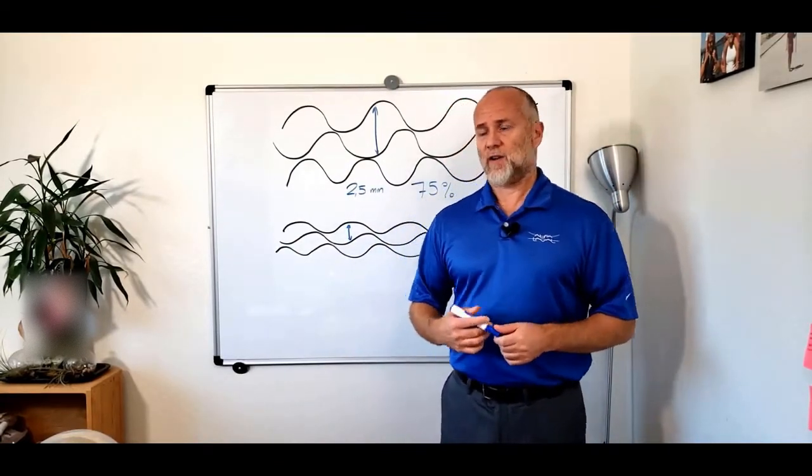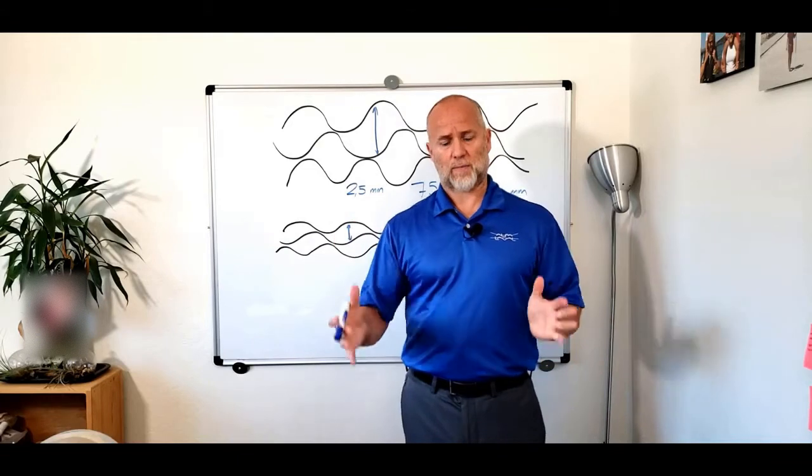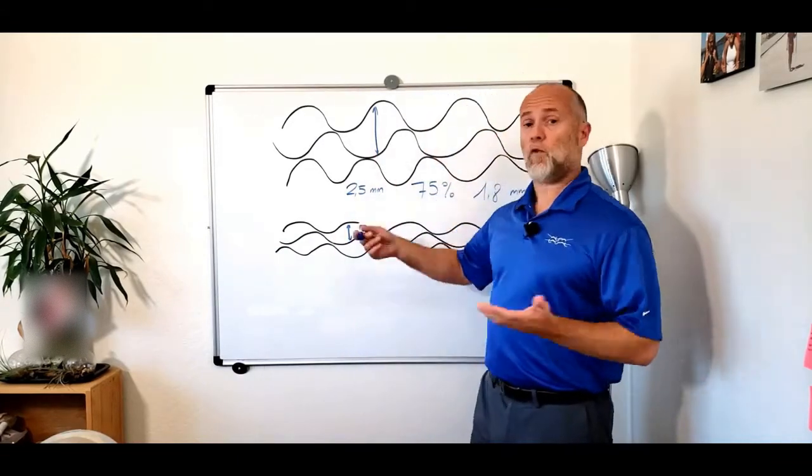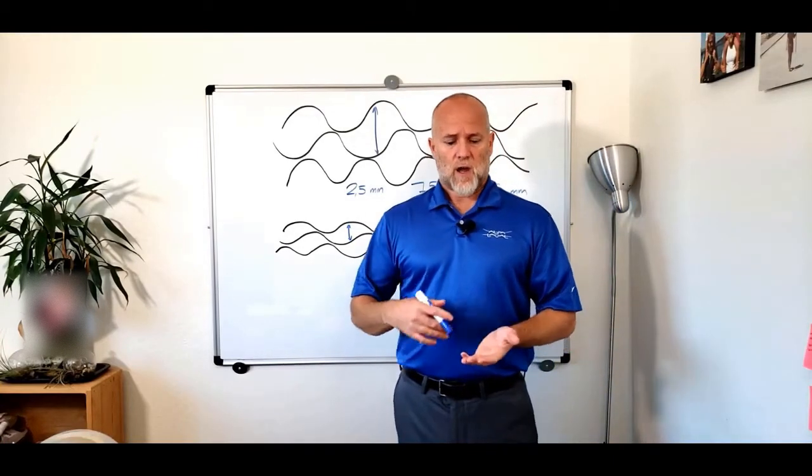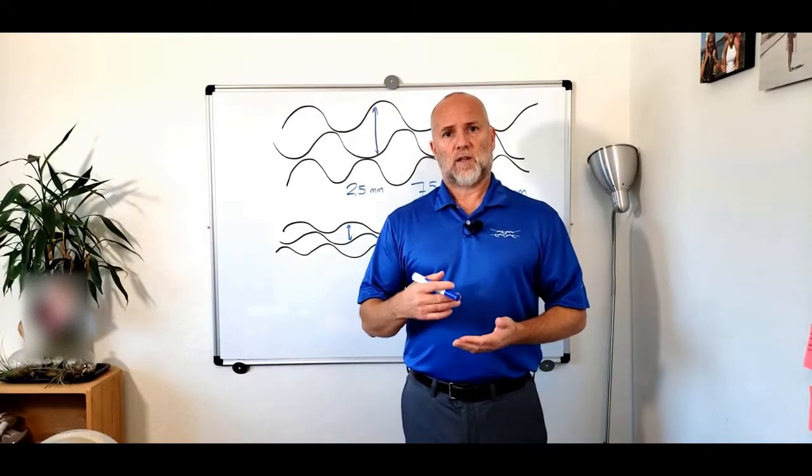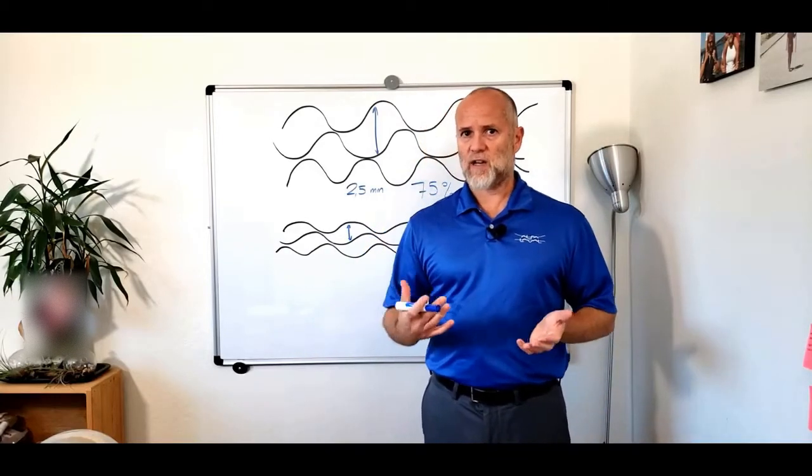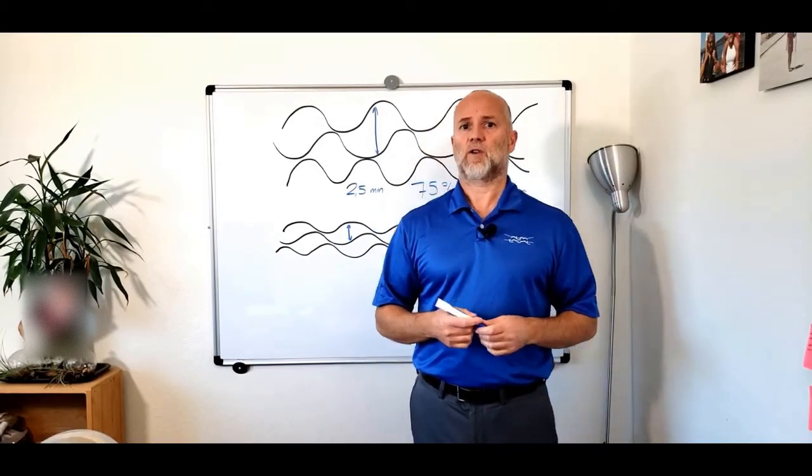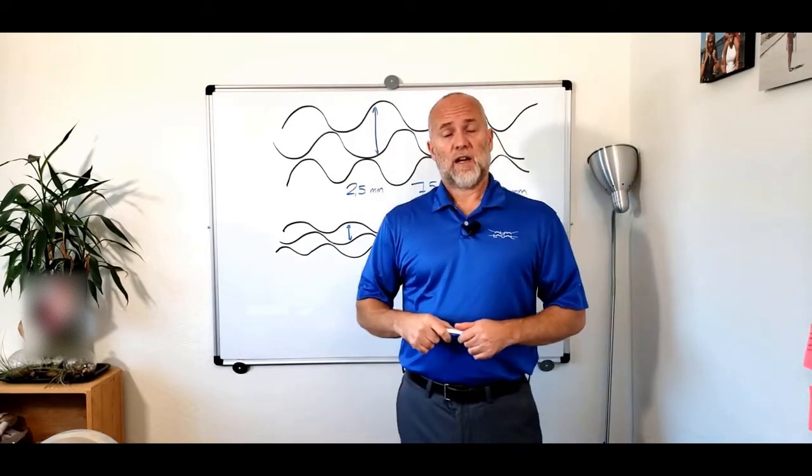Unfortunately, as providers of heat exchangers we are not asked very often what is the size of the channels, and therefore we see strainer filters with meshes that are like 4 millimeters. You understand that in that case you screen out the washers, the bolts and nuts, the gloves, all these very large debris, but the finer particles you end up building them up in the heat exchanger.